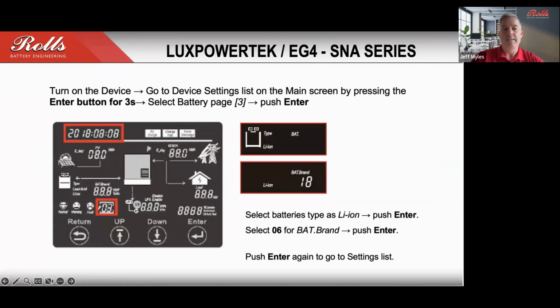Yesterday, I had an individual who contacted us who had connected one of these units, not knowing that it was programmed to work with Victron, and connected it, and then right away, they had an alarm code of 00. And so what we've identified and put into the manual is essentially an explanation of what some of those codes are, and explained that in those conditions, it is a communication problem. Check the cabling, ensure you've connected in the proper ports, but also ensure that the protocol is right. So it is very easy to identify the issue and to be able to change that.